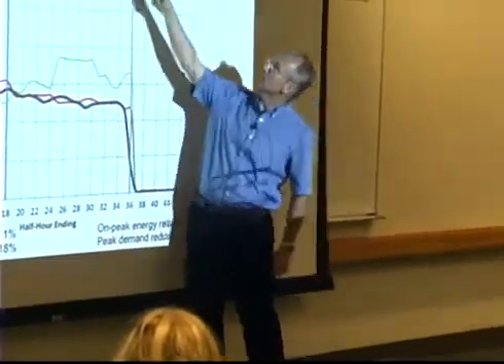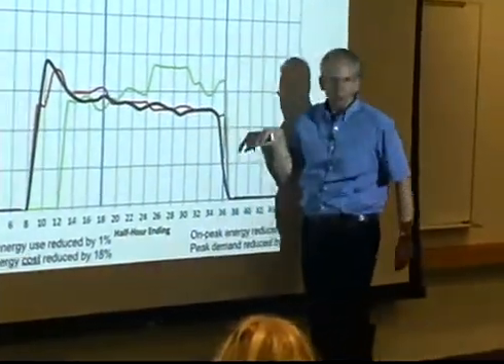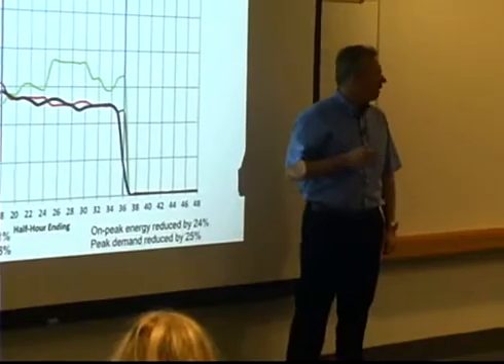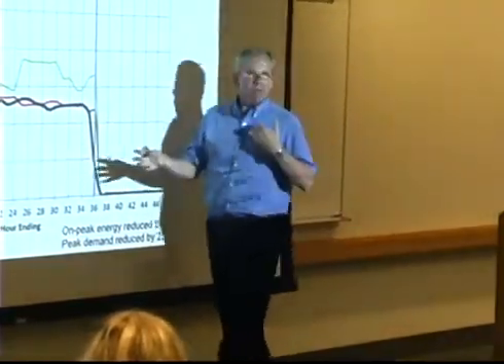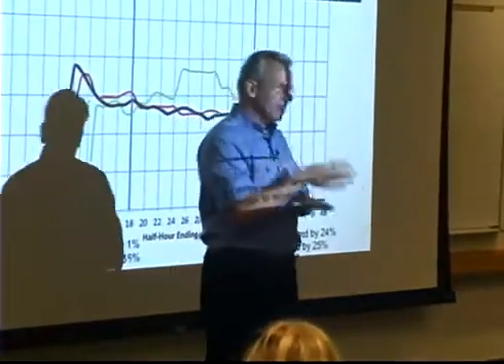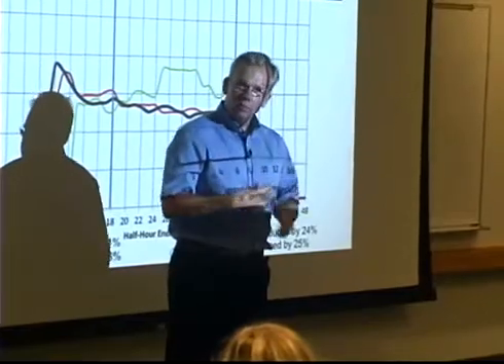In reality, we have observed electricity consumption shown in black here. And you can see a very good match. It's actually not necessarily easy to get to that kind of a match. The beauty of a model is we can go back and say, what would the calibrated building model have done if we hadn't done any pre-cooling, right? If we hadn't applied optimal control.